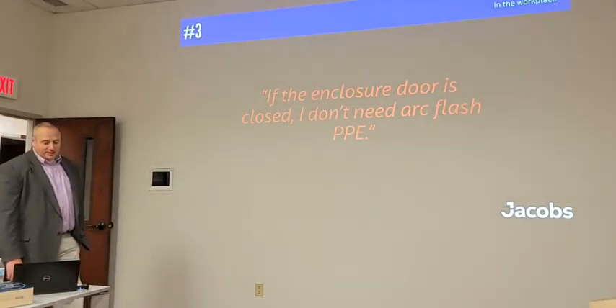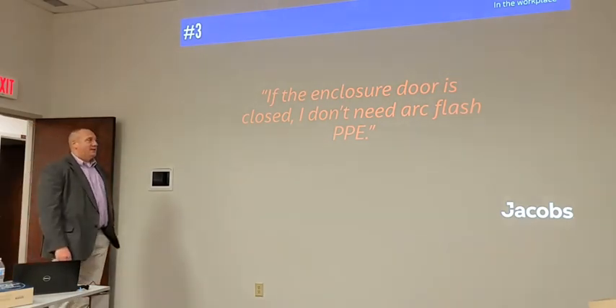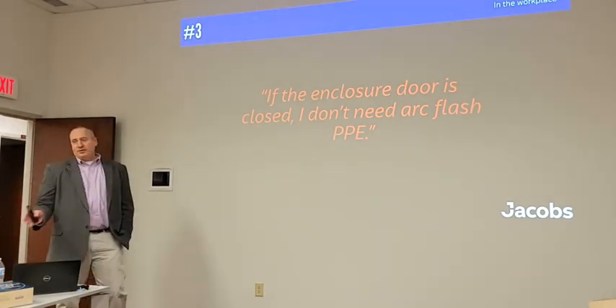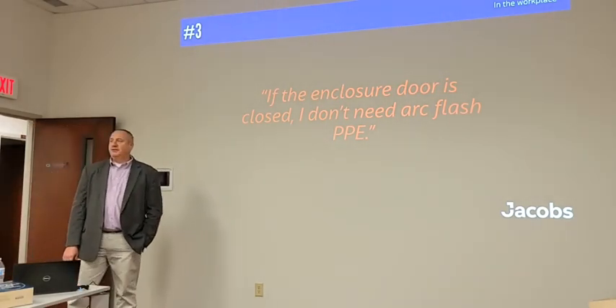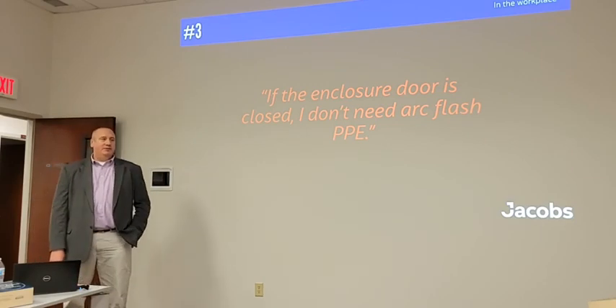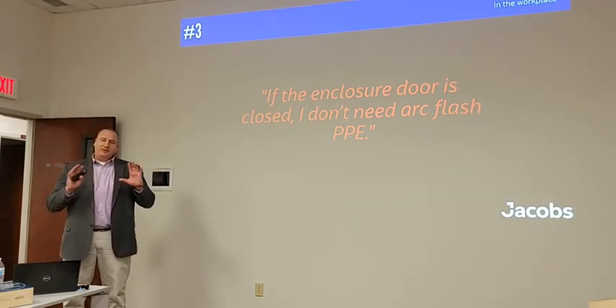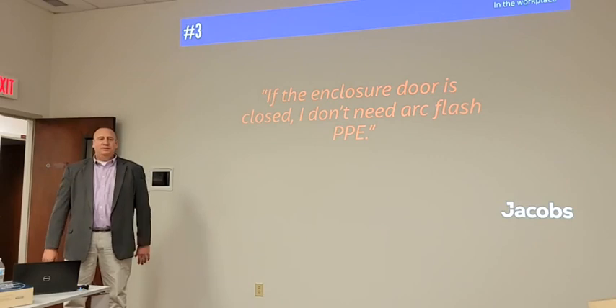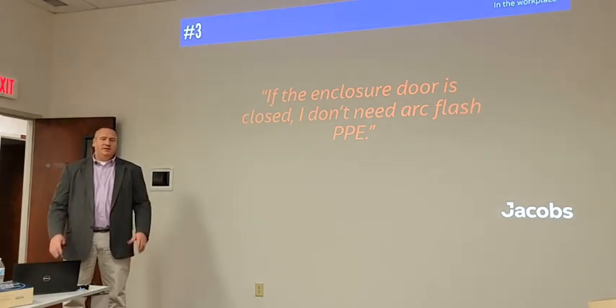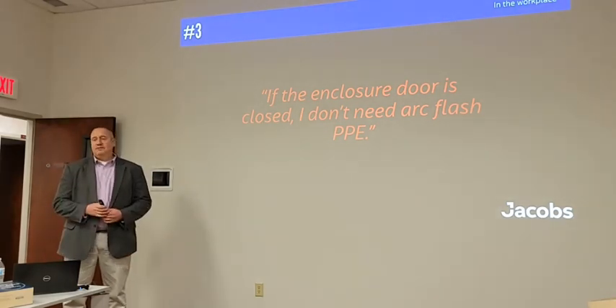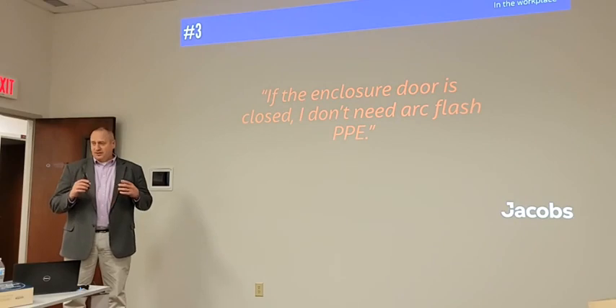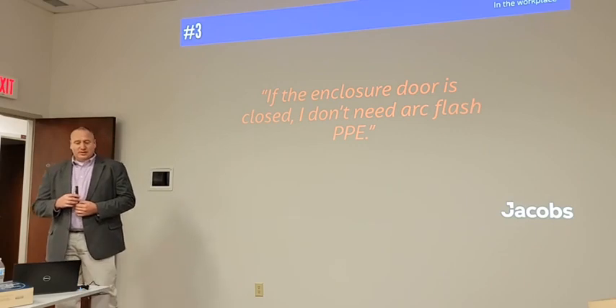If the enclosure door is closed, I don't need arc flash PPE. I used to get this all the time, but it's gotten a lot less common now that people believe that any old type of equipment, if you close the door, then you're safe, that the arc flashes can be contained. And the only time you can be sure of that is if it is arc rated, if it's designed to contain the gear, which would be a newer piece of equipment.